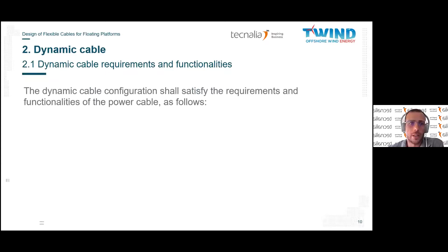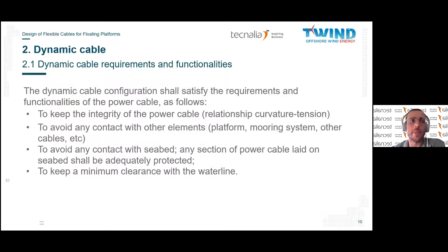The dynamic cable can have different configurations that shall satisfy the requirements and functionalities of the power cable. These are to keep the integrity of the power cable, the famous curvature-tension relationship, to avoid any contact with other external elements like the platform mooring system or other cables, to avoid any contact with the seabed, and to keep a minimum clearance from the water line. As I summarize, to keep the integrity of the power cable and to keep a minimum distance of the cable from other elements.